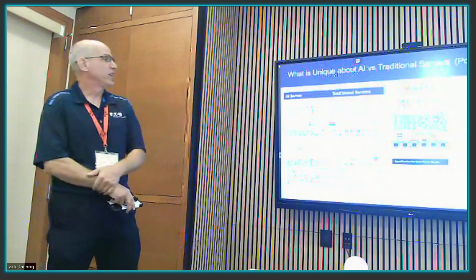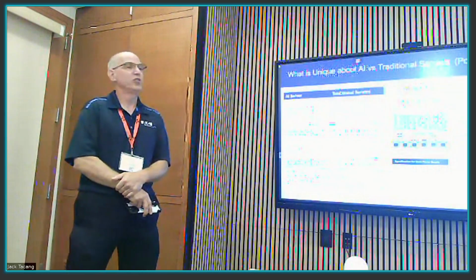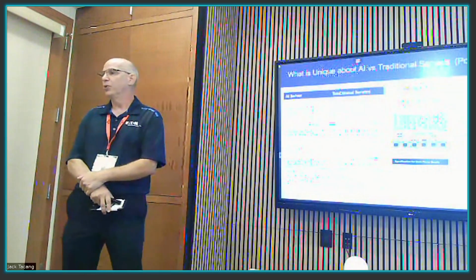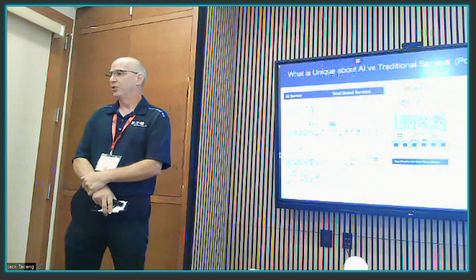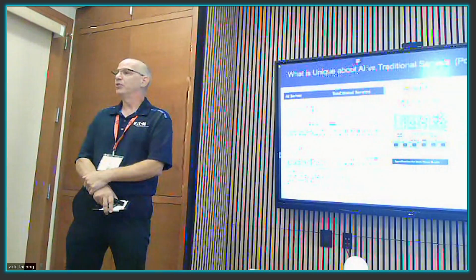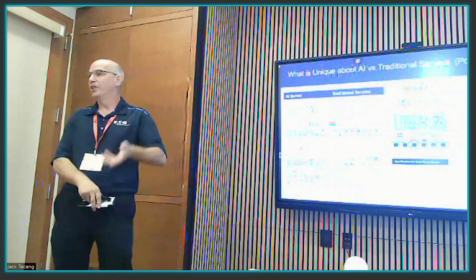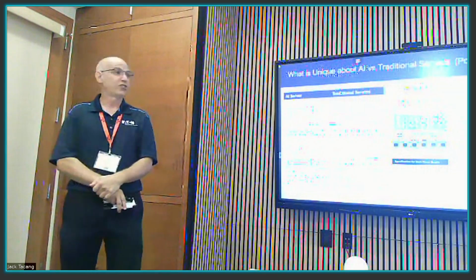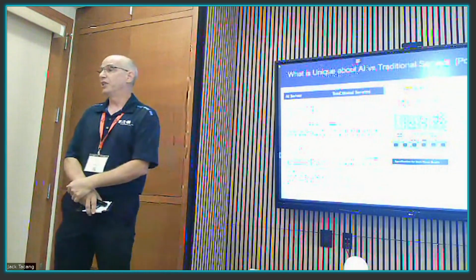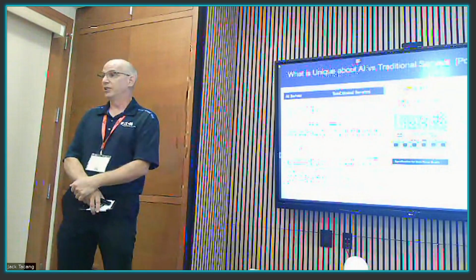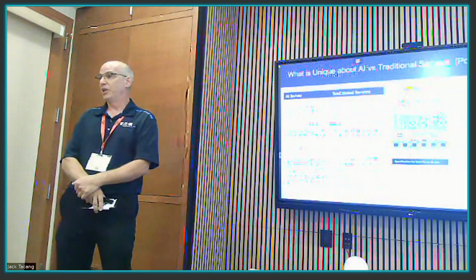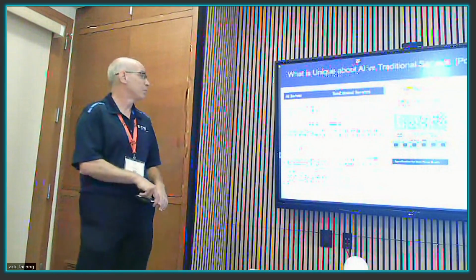In traditional data centers, we're usually powering these boxes with 208, 120 volt power distribution. We're not doing that for AI servers, we're coming with 415, 240, just because of the higher capacities we need higher voltage as well. In the next generation, we're potentially looking at 480, 277 directly, but we just have to wait for the power supplies to be ready, rated for that.